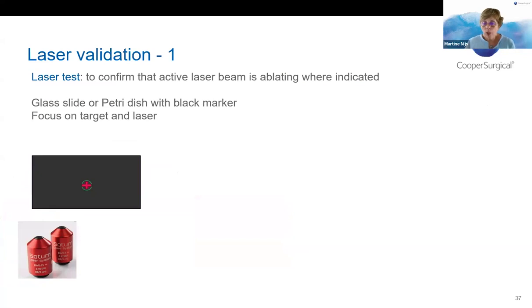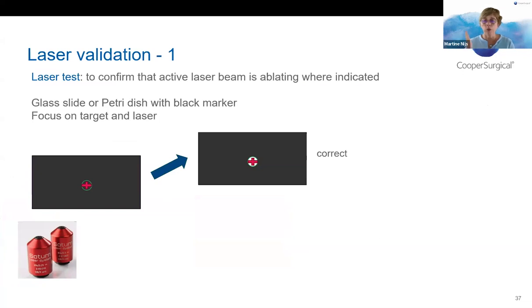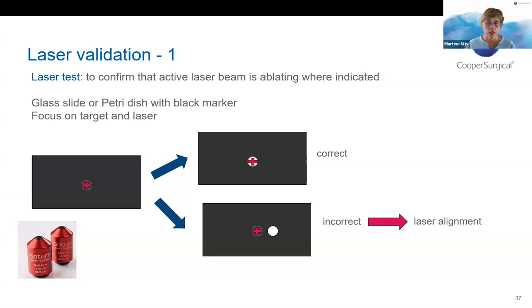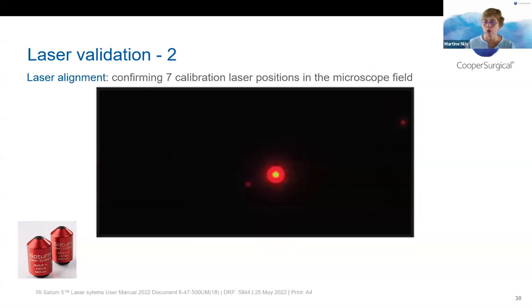Then the validation process: how can you see if it's working, if it's doing what it is intended to do? This is a really easy way to validate your laser, using a glass slide or a Petri dish. Put black marker on these, and then you indicate the target where you want to laser, which is this red crosshair here. We will laser, and if the marker is being burnt away where we have intended it to be, then you have a correct laser setup. If that is not the case, and this is the second example I'm showing you here, that you have a deviation between the point where you want to laser and where the actual lasering is being done, then this is a danger for all your operations that you will do with the laser. So you need to align the laser. It's an easy way to test just prior to each micromanipulation setup before you start the lasering.